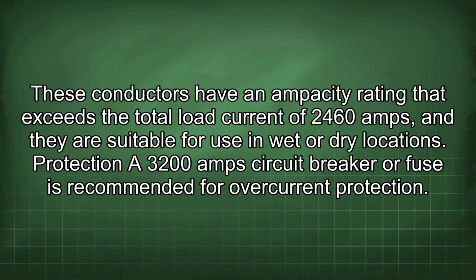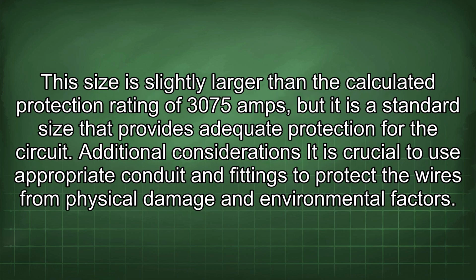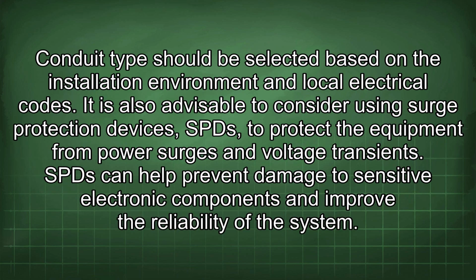Protection. A 3200 amp circuit breaker or fuse is recommended for overcurrent protection. This size is slightly larger than the calculated protection rating of 3075 amps, but it is a standard size that provides adequate protection for the circuit. Additional considerations. It is crucial to use appropriate conduit and fittings to protect the wires from physical damage and environmental factors. Conduit type should be selected based on the installation environment and local electrical codes.